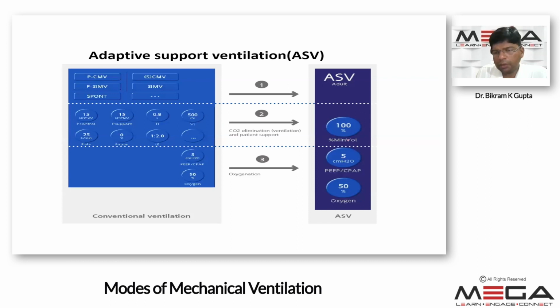But here we are just keeping the percentage of minute ventilation, and 100% means it will give 100 ml per kg of minute ventilation to a patient. It mainly helps with CO2 elimination and patient support. In the conventional ventilator, these parameters help the CO2 elimination and support the patient by achieving the minute ventilation. But in this ASV mode, we just set the minute ventilation, so it helps with CO2 elimination and patient support. So we only have to set one parameter in adaptive support ventilation.